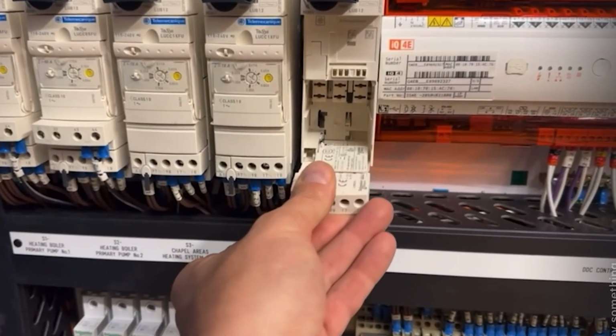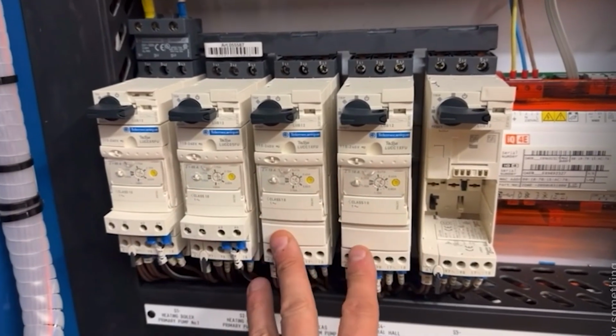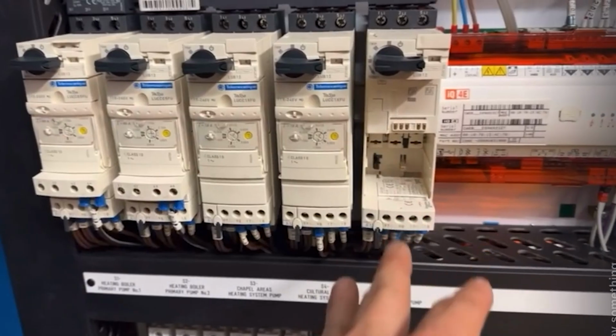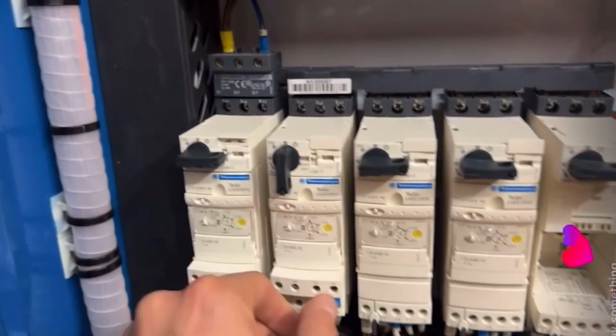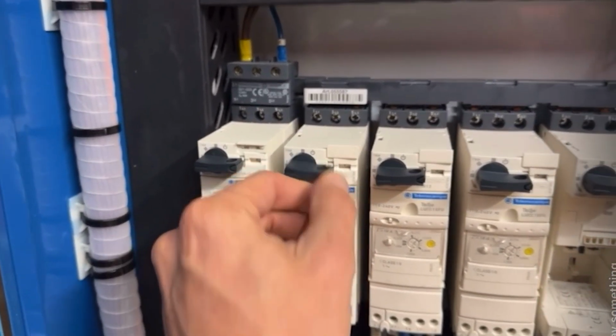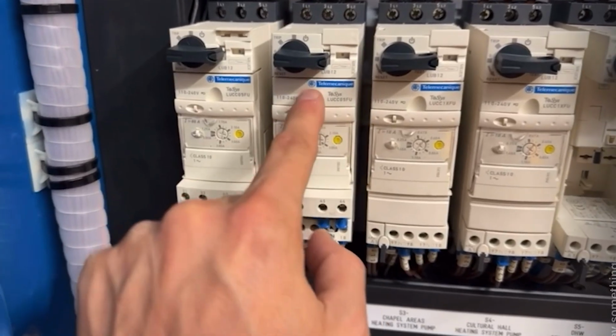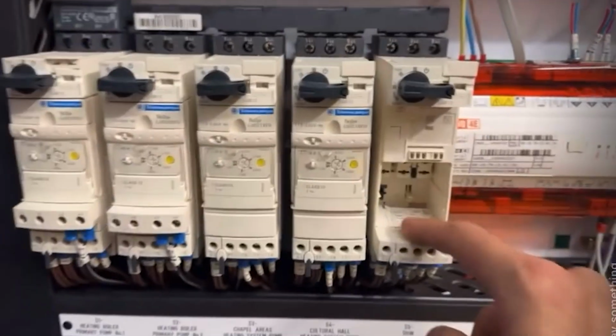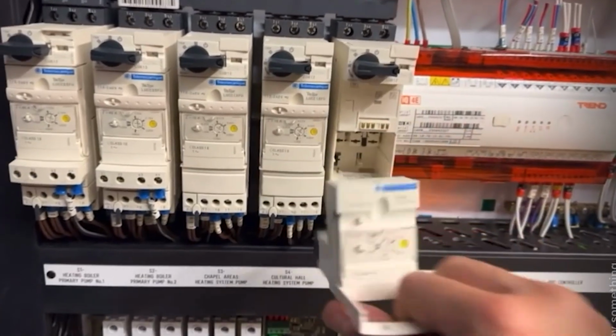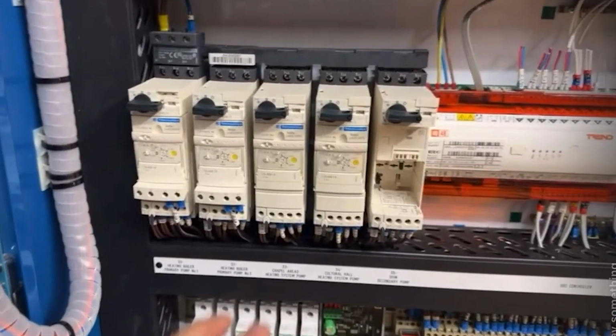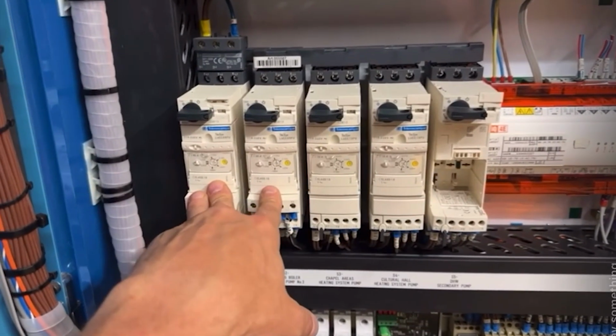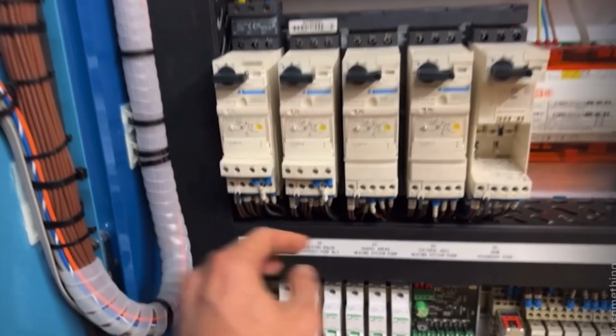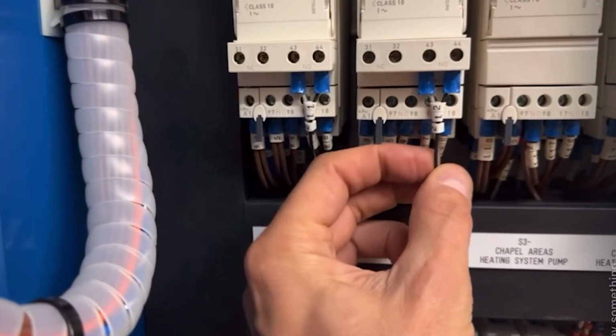So there you go, that's the first introduction to that, but it could easily have its own video, and I will do a separate video on those - they are motor controllers. You've got the on, off, and trip in the middle, there's the overload bit, and what's good about them is if you change this motor and the cable's the right size but the overload's wrong, you can withdraw this motor overload and swap it for the right size. I worked at a company where we used these extensively, the whole site was made out of them, very useful, but difficult to keep spares. I've just noticed there, look, as well.